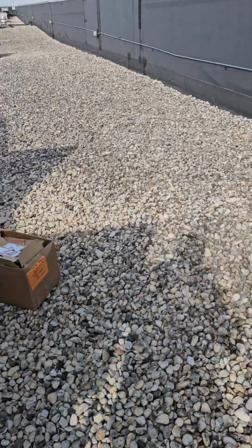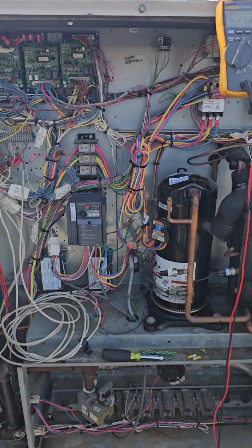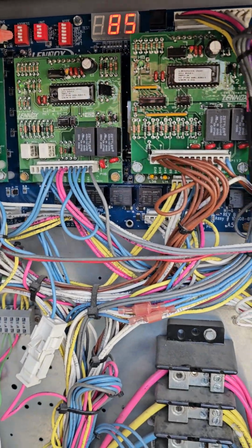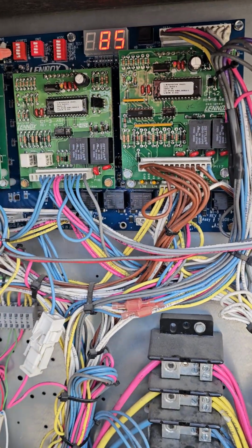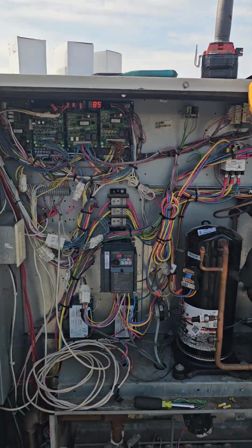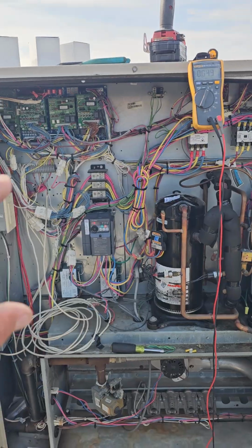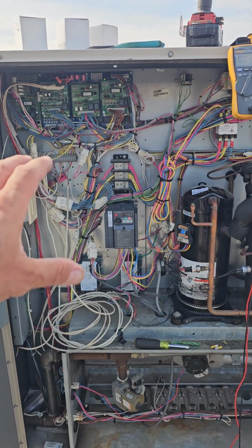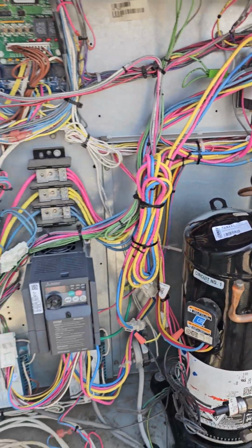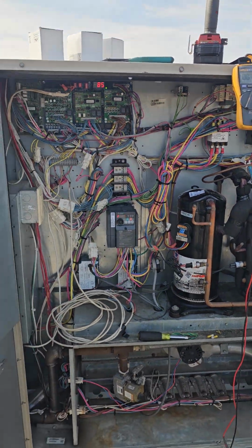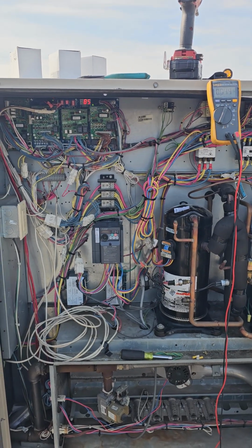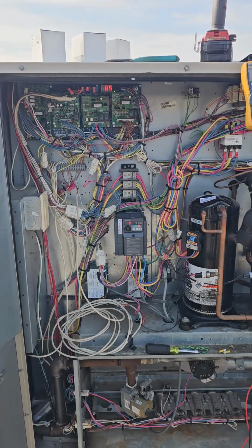Then you can power it back up, and you know now that those parameters that you changed are officially saved in here. I know for a fact if I go back in, it's going to show all the parameters that I saved. And that's it. I mean, it's as simple as that. For the most part, the VFDs, if you ever have to replace one, granted they give you 40,000 feet of wire, which you don't really need, but it's as simple as that. There's really no programming that needs to be done in the VFD itself.